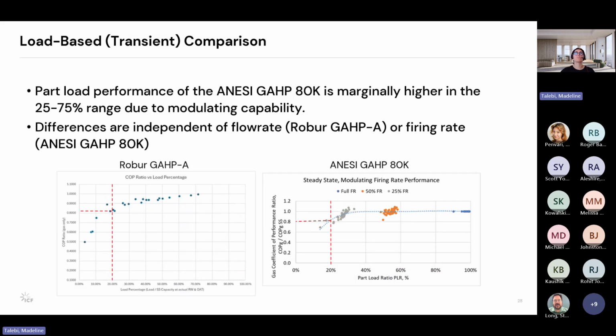And then looking at the part load performance comparison, the differences are going to be independent of the flow rate and the firing rate. We see in this case for the Robur unit, we're at about 0.82, I would predict. And similarly, we're about 0.82, 0.8 in this case. So again, minimal difference between the two units for that load-based testing, which would most likely reflect actual field data, since you would never have something operating under steady state. In a field application, there would be some variation in the load demand, just the nature of the systems themselves, and of course the user.